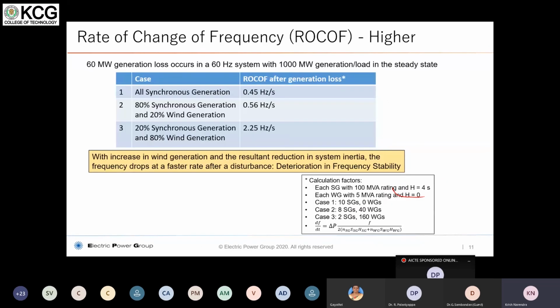Now, let us look at how it impacts the rate of change of frequency, that is ROCOF. In case 1, as shown here, when you have all synchronous generation, you can see that the frequency is dropping at only 0.45 hertz per second. If you have 80% synchronous generation and 20% wind, the rate of change of frequency is already higher, 0.56 hertz per second. And if we change the ratio to only 20% synchronous generation and 80% wind and solar, you can see that the ROCOF goes to a very high value, and this value is not acceptable as of now because of the instability, the protection system that operates, and load shedding scheme operation.